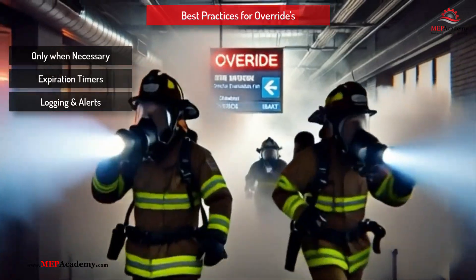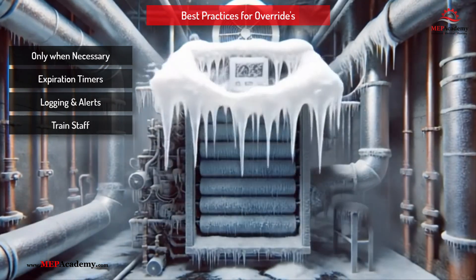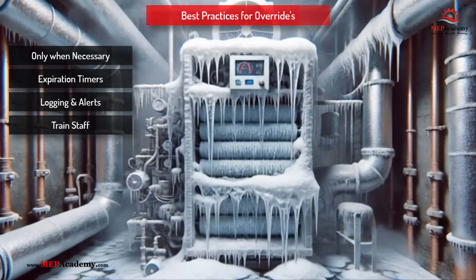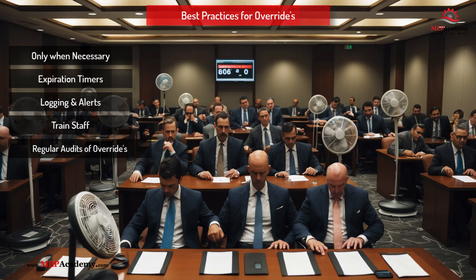Best practices for override management: To prevent override-related failures, the following best practices should be implemented. Use overrides only when necessary — avoid casual overrides and use them strictly for troubleshooting, maintenance, or emergencies. Set expiration timers so overrides reset after a predefined period. Implement logging and alerts to track all overrides in the building automation system and alert operators of prolonged or unsafe overrides. Train facility staff to ensure all personnel understand when, why, and how to properly use overrides. Regularly audit overrides by conducting periodic system audits to identify and remove forgotten overrides.